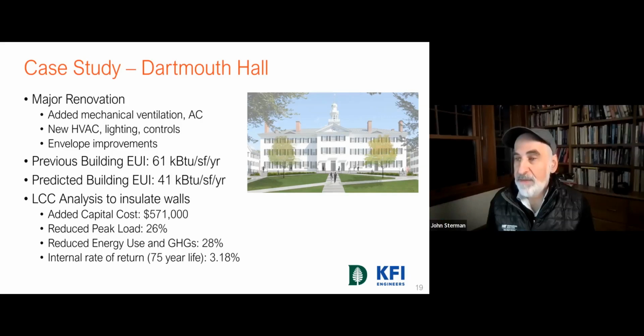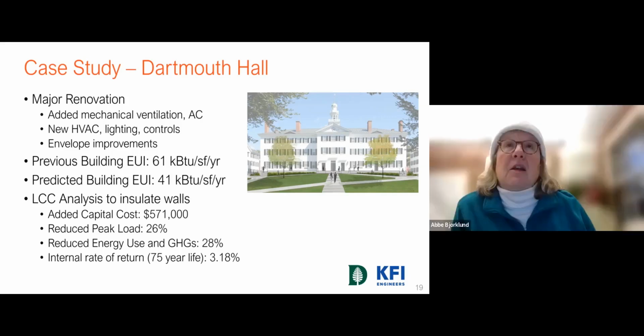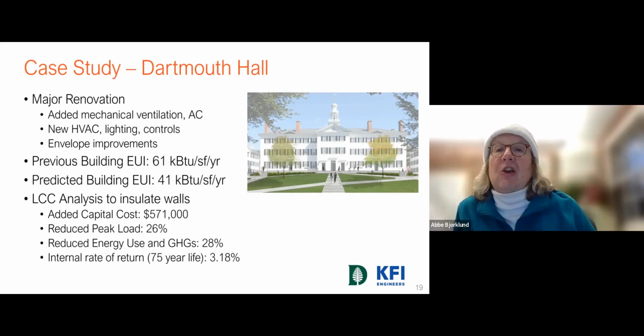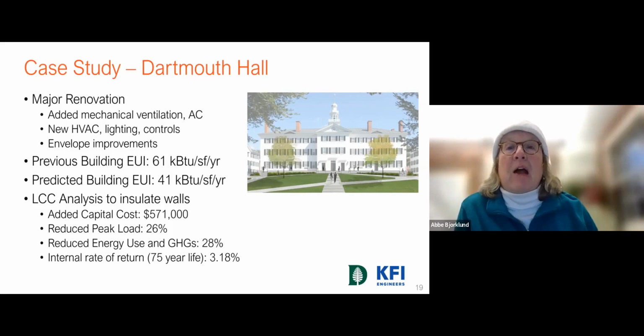Is that an HRV or ERV system? It is a dedicated outdoor air system with heat recovery. So the air system is sized just to provide ventilation, and the balance of the heating and cooling requirements are provided by water systems. That's a general policy we've been following for HVAC systems too, because heat transfer can happen much more efficiently through water than through air.